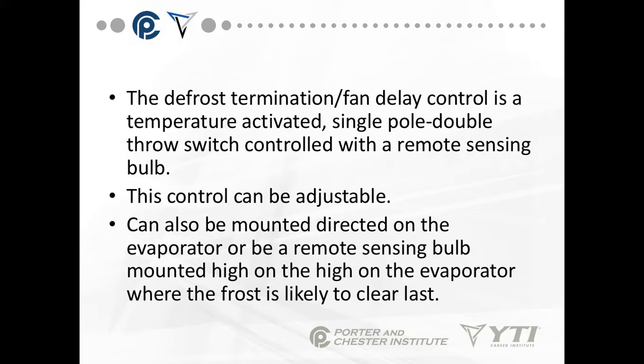The defrost termination and fan delay control is a temperature-actuated, single-pole, double-throw switch with a remote sensing bulb. This control can be adjustable. It's most often mounted directly to the evaporator, but it can also use a remote sensing bulb mounted high on the evaporator where the frost is likely to clear last — in other words, where the frost is going to stay the longest.